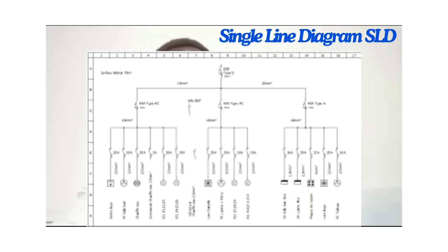So we should be able to make sure that we lay out the load schedule, put together, and the SLD, so that while we are reading our drawings, we know how to interpret to carry out the execution of work on site. That makes us able to have a bigger picture when we are interpreting the drawings, so that you go through the layout, you get the load schedule, you get the SLD, you put them all together. While you're reading your layout, you go through the load schedule as well to identify the different circuit reference. Does it match with the layout? And then also you check as well the size of the cable or the size of the wire, so that while you're pulling, you know that what you're doing is correct.